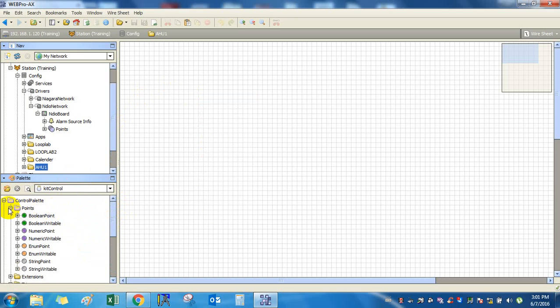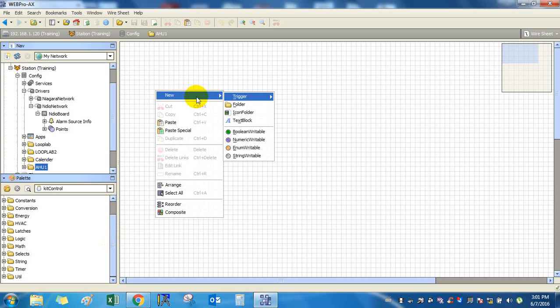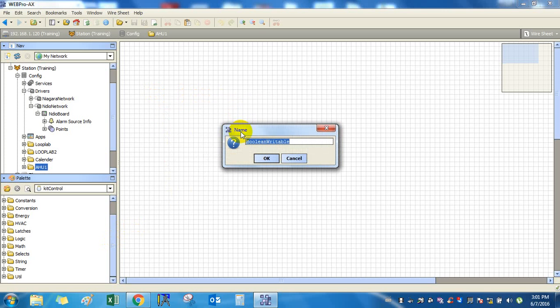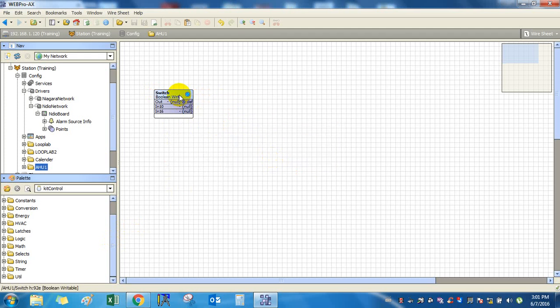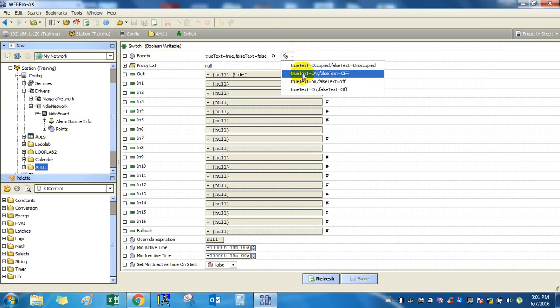So this is a simple control loop to control the space temperature, and based upon the space temperature your heating and cooling will operate, your fan will run and dampers will modulate. So let's start. First, add a switch button: new, add a boolean writable, name it as switch. Double click it and change the facets to on off. True text as on, false text as off.